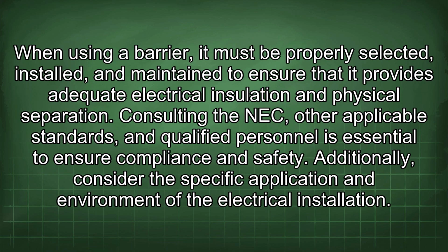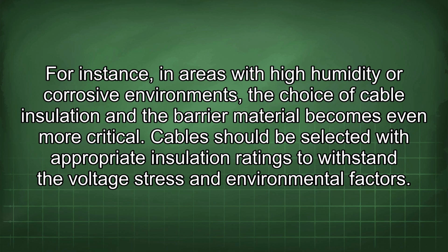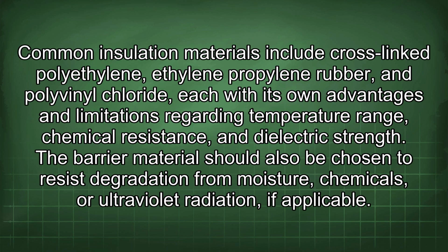When using a barrier, it must be properly selected, installed, and maintained to ensure that it provides adequate electrical insulation and physical separation. Consulting the NEC, other applicable standards, and qualified personnel is essential to ensure compliance and safety. Additionally, consider the specific application and environment of the electrical installation. For instance, in areas with high humidity or corrosive environments, the choice of cable insulation and the barrier material becomes even more critical. Cables should be selected with appropriate insulation ratings to withstand the voltage stress and environmental factors. Common insulation materials include cross-linked polyethylene, ethylene propylene rubber, and polyvinyl chloride, each with its own advantages and limitations regarding temperature range, chemical resistance, and dielectric strength.